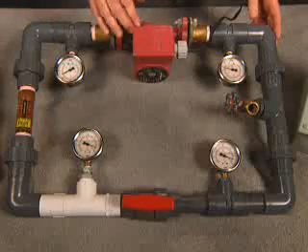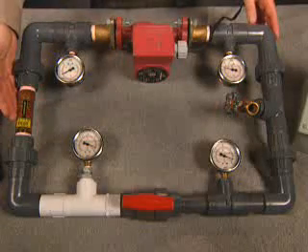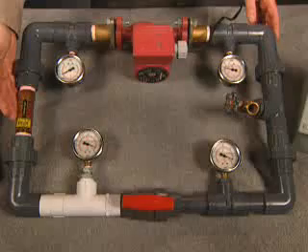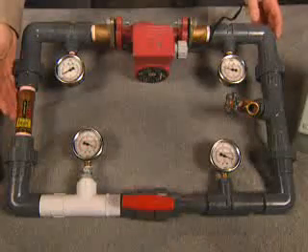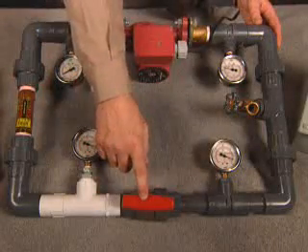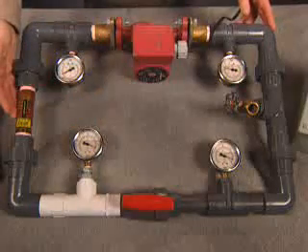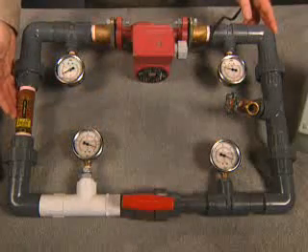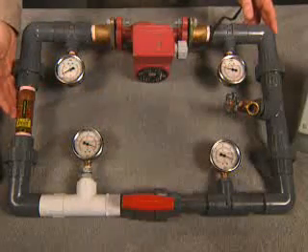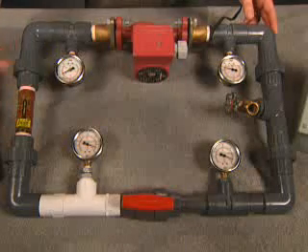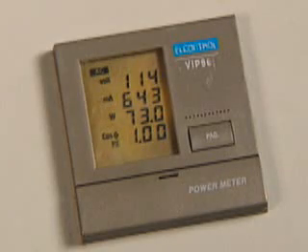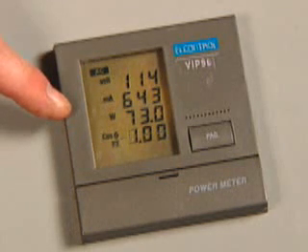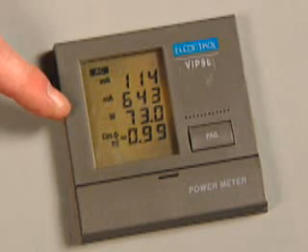The pump is circulating 5 gallons of water per minute through the system. The initial reaction most people have is to reduce the flow rate by throttling the valve. We want to achieve a certain flow rate in this part of the system, which is actually the flow meter. But in a real application, it can be a heat exchanger. Right now, at full speed with the valve open, the system is consuming 73 watts to generate 5 gallons per minute of flow. Let's compare two methods to achieve the lower flow rate.